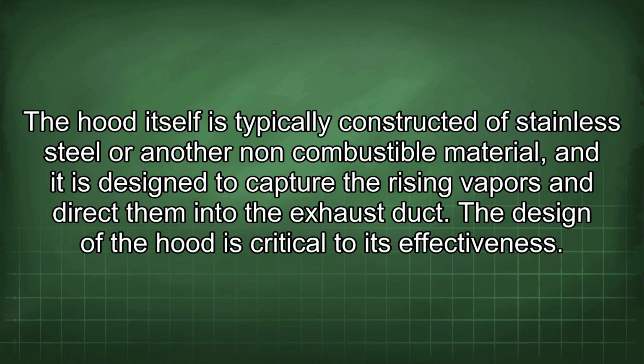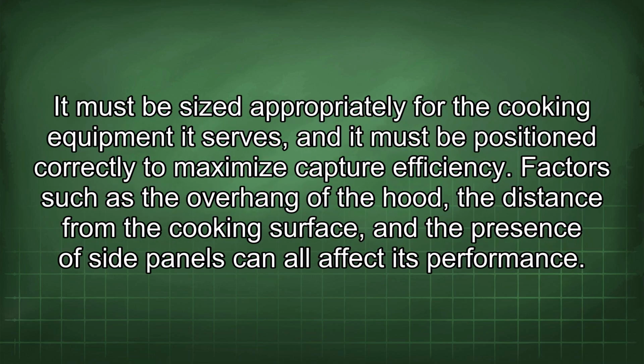The design of the hood is critical to its effectiveness. It must be sized appropriately for the cooking equipment it serves, and it must be positioned correctly to maximize capture efficiency. Factors such as the overhang of the hood, the distance from the cooking surface, and the presence of side panels can all affect its performance.